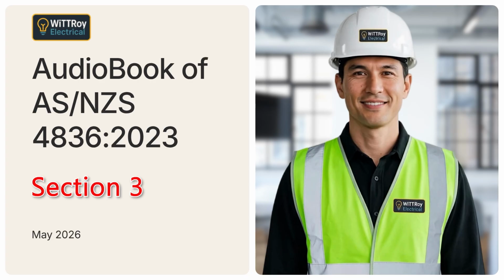Clause 3.1.4.3 Tags. Clause 3.1.4.3 explains the use of tags. Tags must be attached with a lock, string, or tie. The writing on the tag must be clear, readable, and permanent. PVC tape must not be used to secure a tag. If a formal permit system is used, the correct sign-on and tagging procedure must be followed. A tag is a safety communication device. It tells other people that equipment must not be operated, and it helps identify who is involved in the isolation.